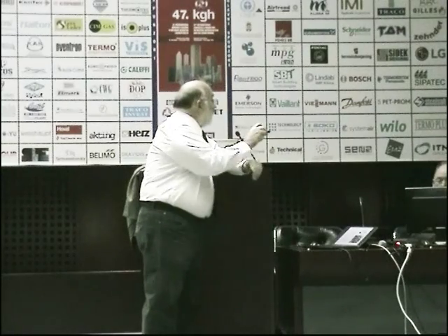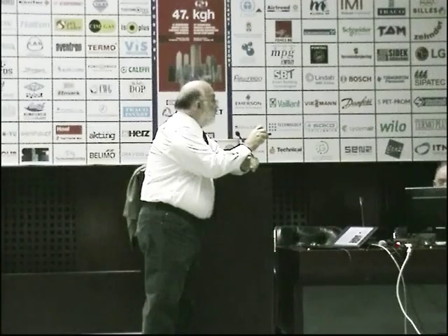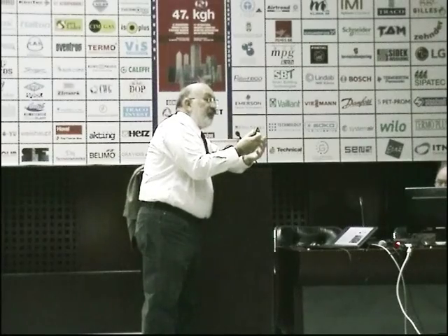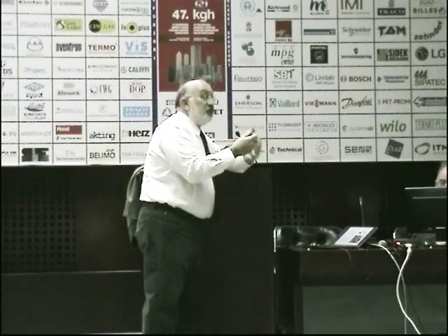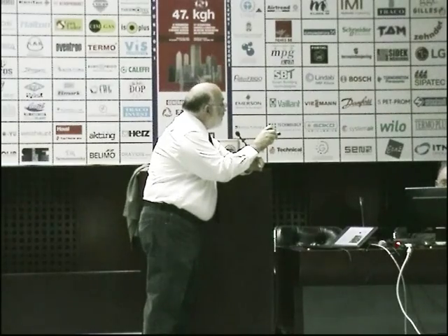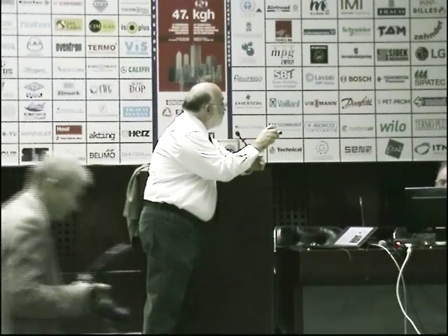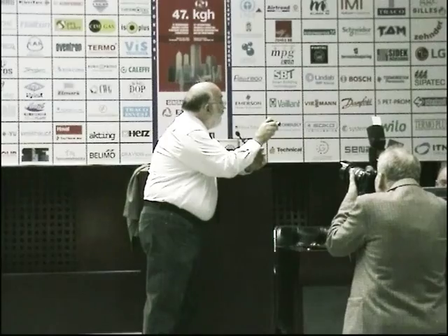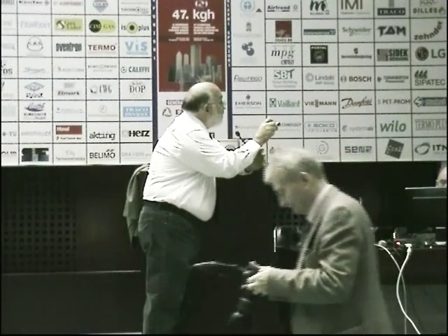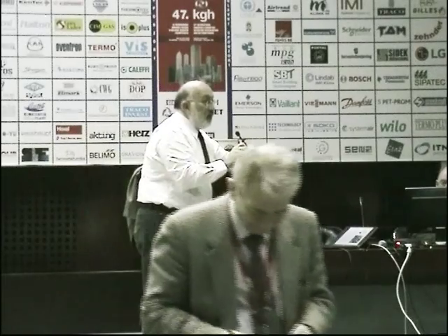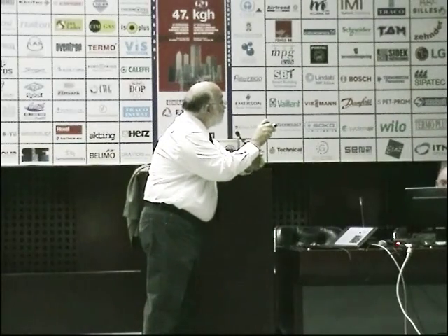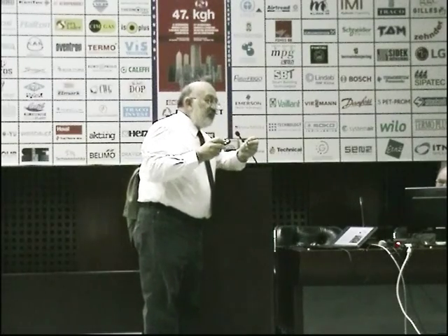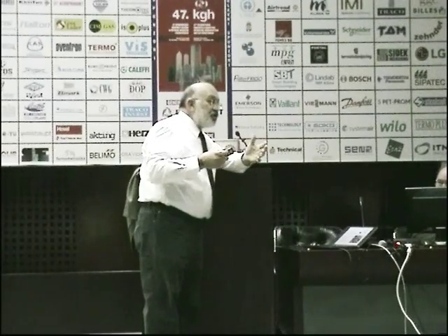Then we put the flange and put the sight glasses. That wasn't enough. Then we made a transparent chamber to be able to watch what is happening in the compressor discharge valve, and I'll show you some videos. And then this is a discharge tube, and this part of the tube here is transparent. We put here a high-speed camera, put a light source, and then around we go and measure with this laser. We measure the thickness of the film. And with the high-speed camera, we try to measure how much oil is in the droplets. That means how many droplets, what is their velocity, what is the distribution, and so on.